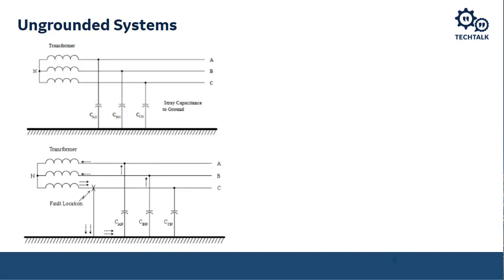Let's first talk about an ungrounded system. There is no fault current when you have a phase-to-ground fault because there's no path to ground. There might be a limited amount because of our stray capacitance to ground, but it's going to be very, very small and it's going to be undetectable. So we're not going to be able to provide ground fault protection with overcurrent relays because the ground fault current is either non-existent or almost undetectable.